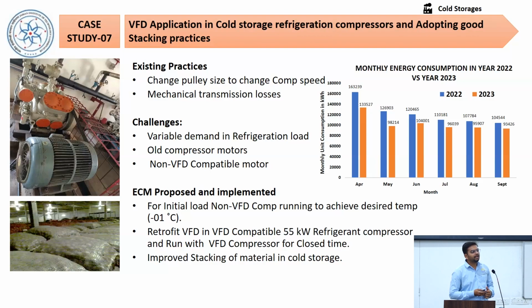Initially, the industry was using all the compressors all the time, depending upon the temperature. But we recommended that the industry have a compressor with VFD retrofitting. But the industry has very old motors, 20-25 years old, and the compressor systems are also old. Only one compressor is compatible with VFD, so they implemented the VFD on that compressor. Whenever there is charging or discharging of material, when the heat loss is more, they also run the non-VFD compressors.